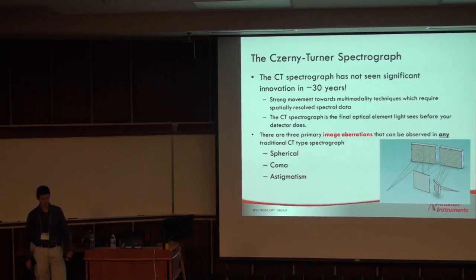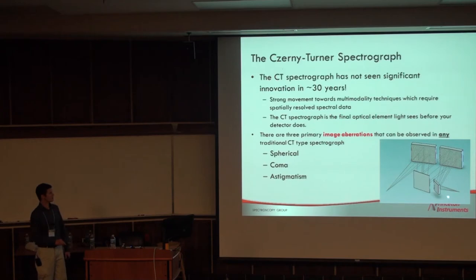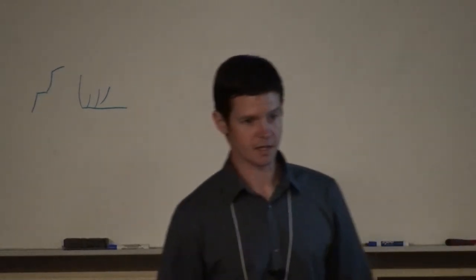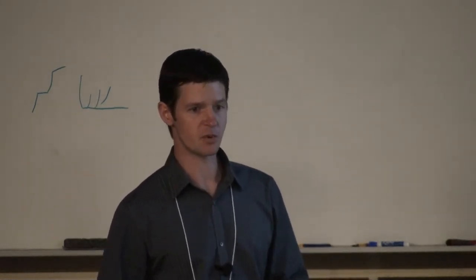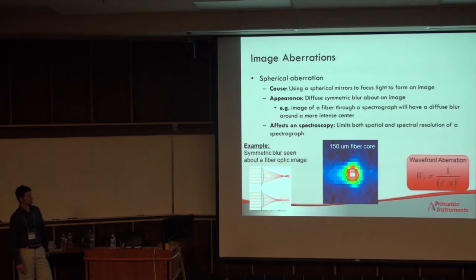For about as long as I've been alive, this instrument hasn't changed, and to me that was really interesting. There is a strong movement towards multi-modality techniques that require spatially resolved spectral data — you want to acquire data in a two-dimensional array at the focal plane. The major problem with this instrument is image aberrations. The three first Seidel aberrations that destroy an image are spherical aberration, coma, and astigmatism, listed in order of severity — and these are the three main players in the Czerny-Turner spectrograph.